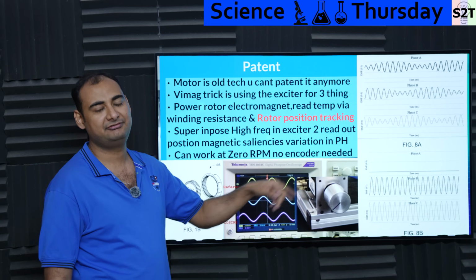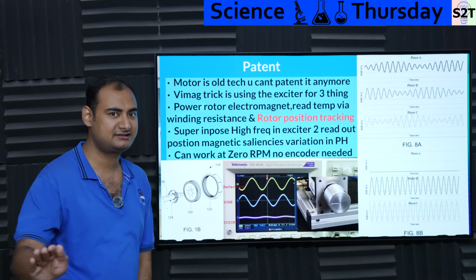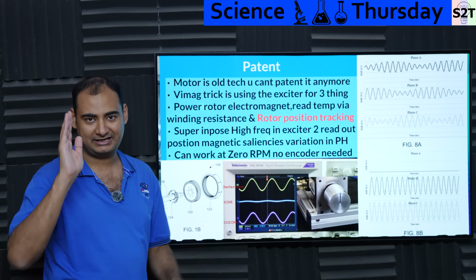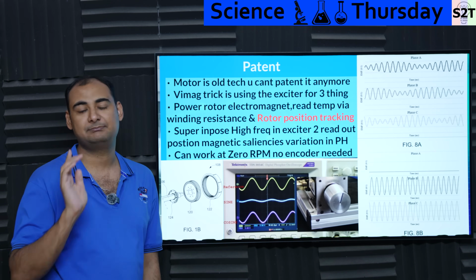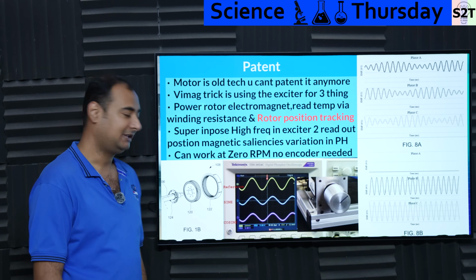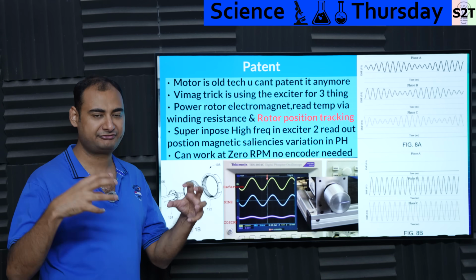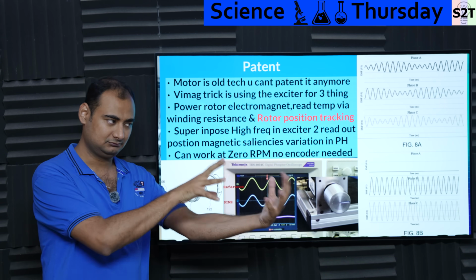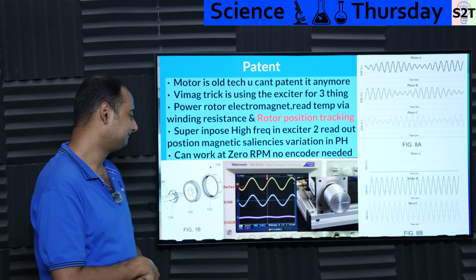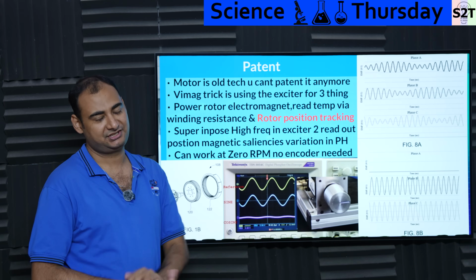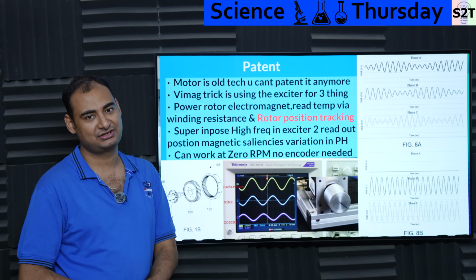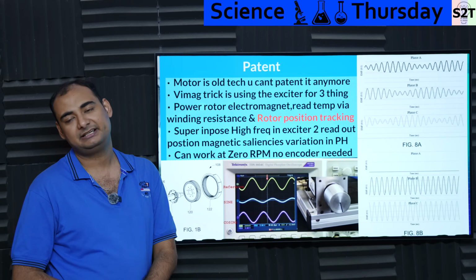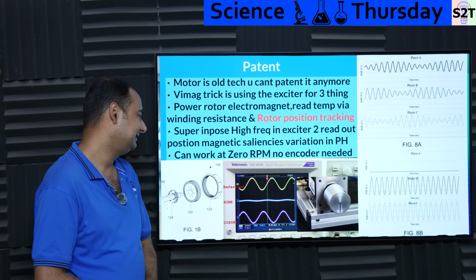So this is how they figure out at 0 RPM, meaning dead start the system, it can figure out exactly where the magnetic poles are. Because it's deadlocked with the shaft, it knows the exact rotor position, exactly. This is the black magic they have. This is what they've patented, rotor and position tracking. I have no idea why nobody is talking about this, but it is what it is.